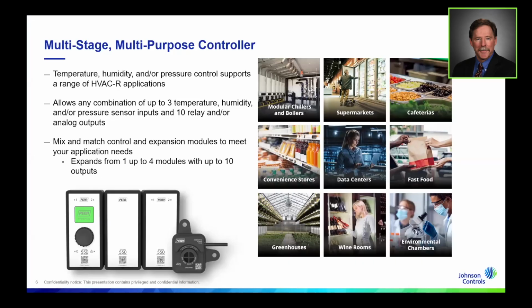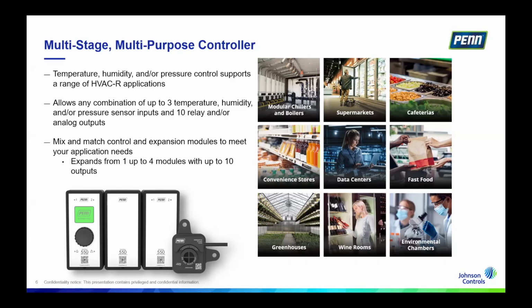Yeah, this is just a very small subset of the applications that is capable through System 550. As Josh said, when you have inputs of up to 3 temperature, humidity, and pressure inputs, and keep in mind that the pressure side can be either differential pressure or it can be system pressure. So when we take a look at those, starting in the 9 squares that we have here, we see a lot of applications with modular chillers and boilers where you're typically controlling water loop temperature.